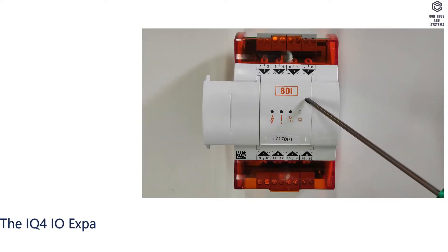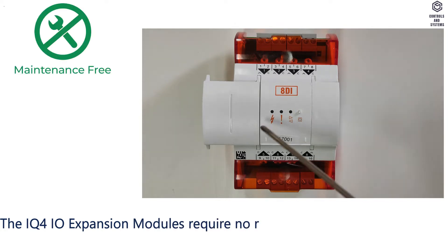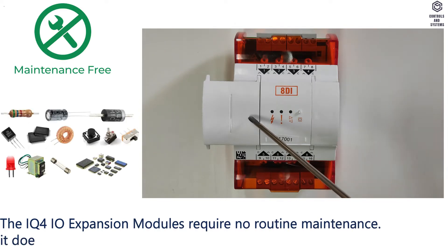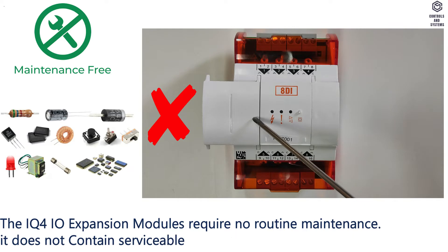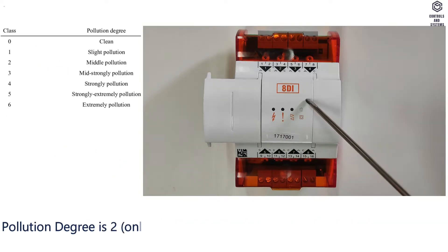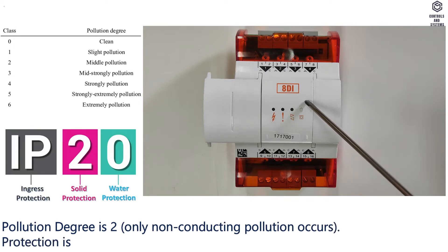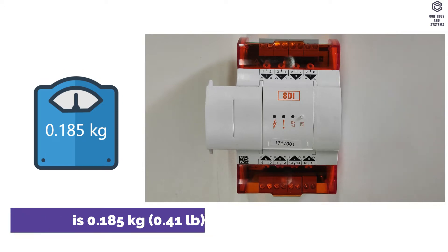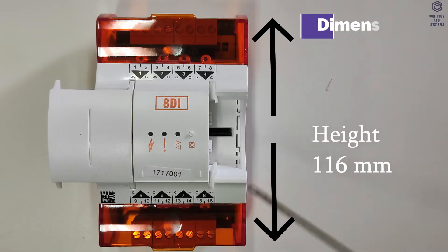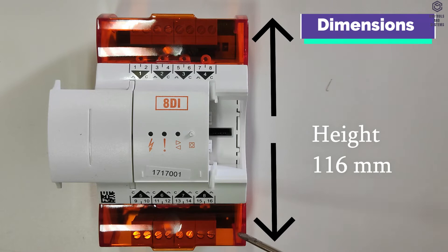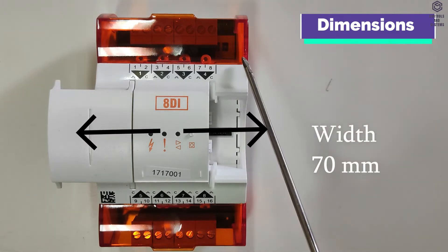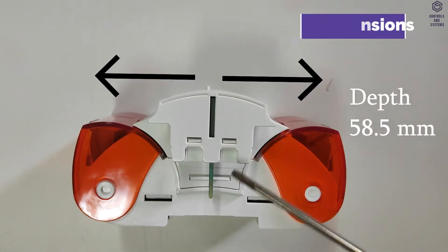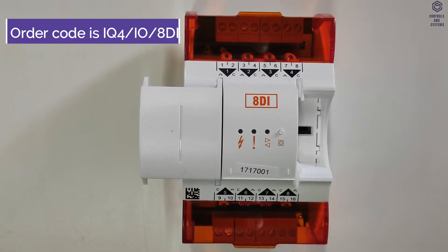The IQ4 I/O expansion modules require no routine maintenance and do not contain serviceable parts. Pollution degree is 2 — only non-conducting pollution occurs. Protection is IP20. Weight is 0.185 kg. Dimensions: height 116 mm, width 70 mm, depth 58.5 mm. Order code is IQ4 I/O 8 D.I.